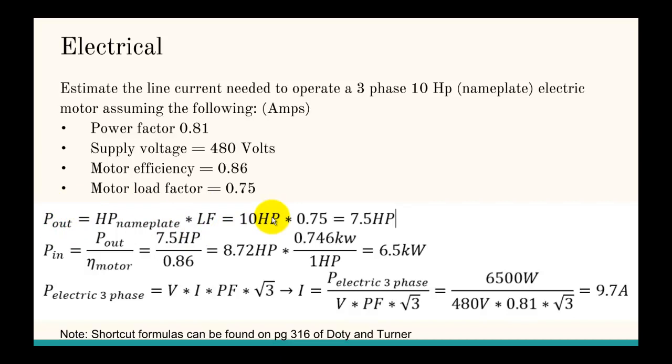So, the output power of this motor is the nameplate horsepower times the motor load factor. And then, to get the input power, you divide by the motor efficiency. So, you divide the output power by the motor efficiency. And, in this case, I just converted that to kilowatts.